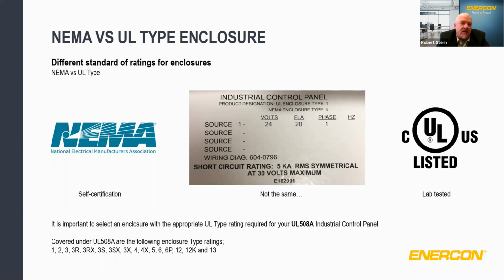So you see here in the middle, you could have a label that shows that this particular enclosure might be NEMA enclosure type 4, but because it was not tested to UL, it only carries a UL type 1 rating. And this is what would be applied for that particular product. Under the UL 508A standard, there is a wide range of different classifications under type ratings based on the varying degrees of their ability to withstand, again, particulate, non-corrosive gases, ice, sleet, etc. Next slide, please.